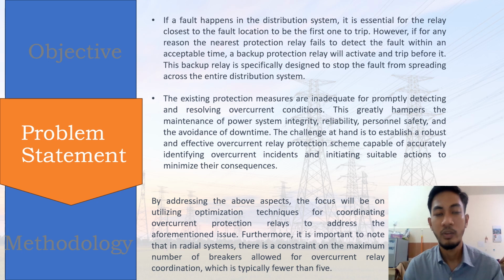By addressing the above aspects, the focus will be on utilizing an optimizing technique for coordination of overcurrent protection relays to address the coordination issue. Furthermore, it is important to note that in a radial system there is a constraint on the maximum number of breakers allowed for overcurrent relay coordination, which is typically fewer than 5.